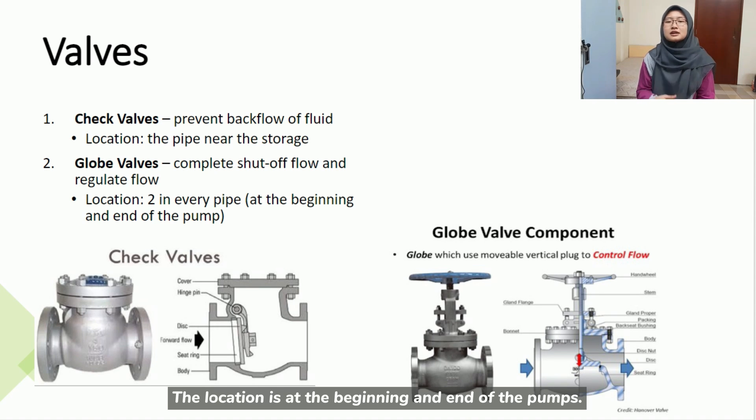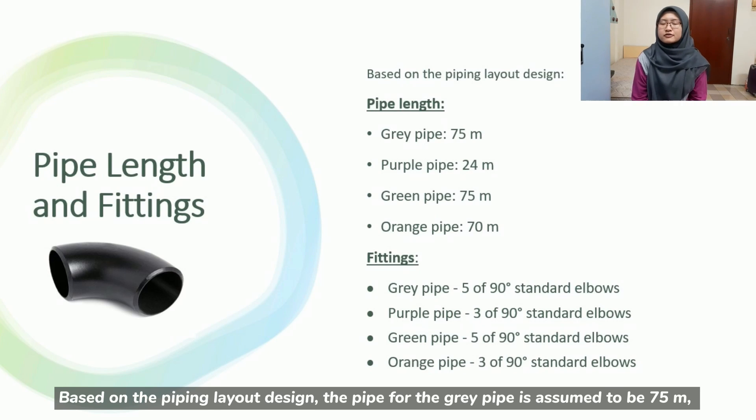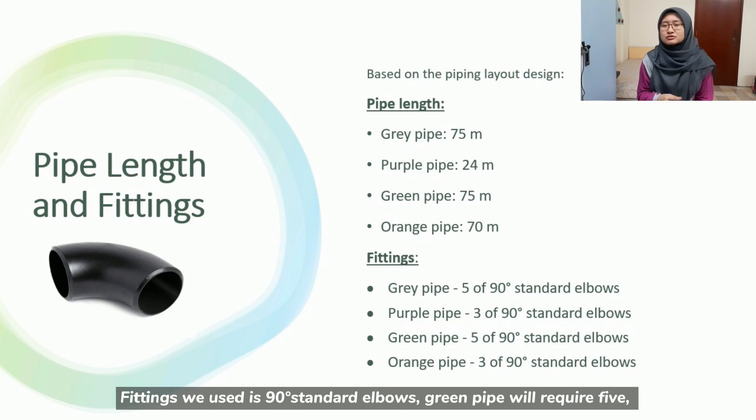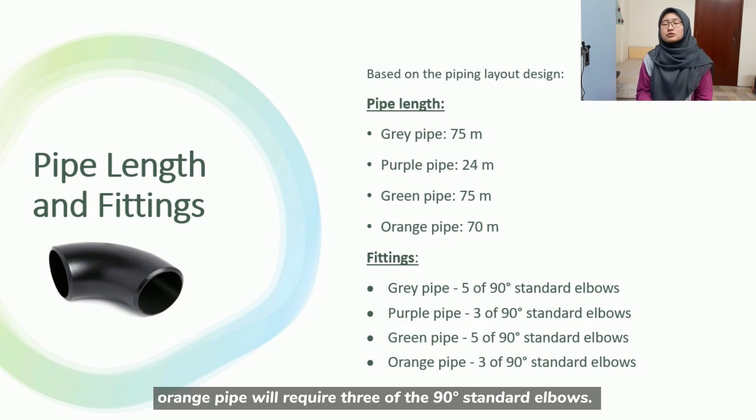Based on the piping layout design, pipe length for the grey pipe is assumed to be 75 meter, purple pipe is 24 meter, green pipe is 75 meter, orange pipe is 70 meter. The fittings we use is 90 degree standard elbows. Grey pipe is 5, purple pipe will require 3, green pipe will require 5, orange pipe will require 3 of the 90 degree standard elbows.